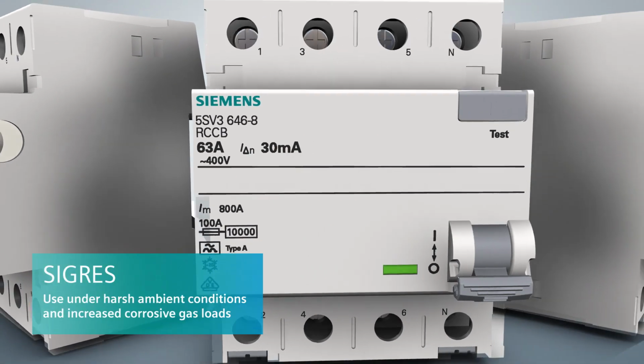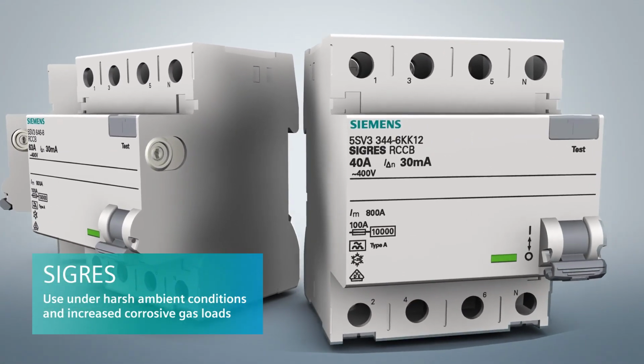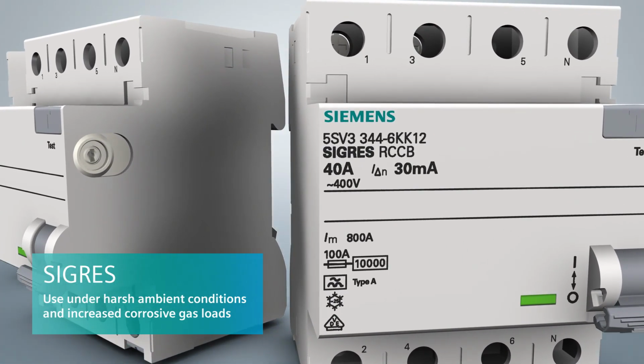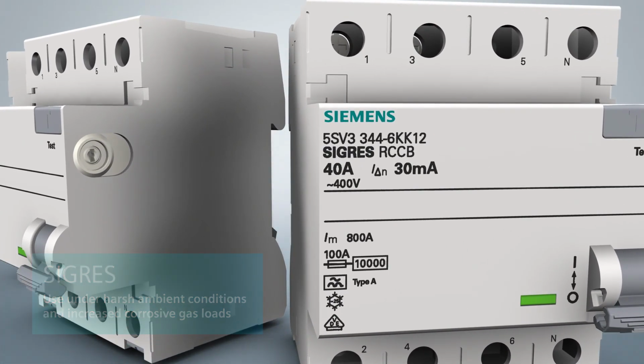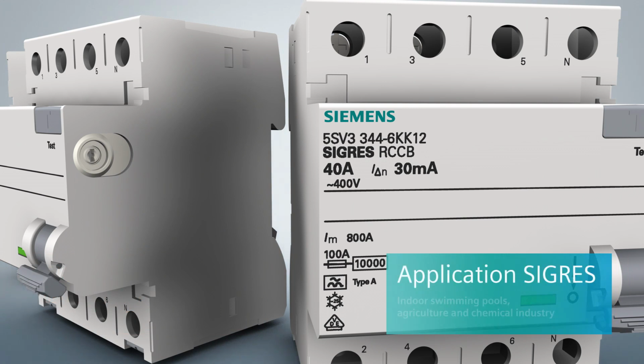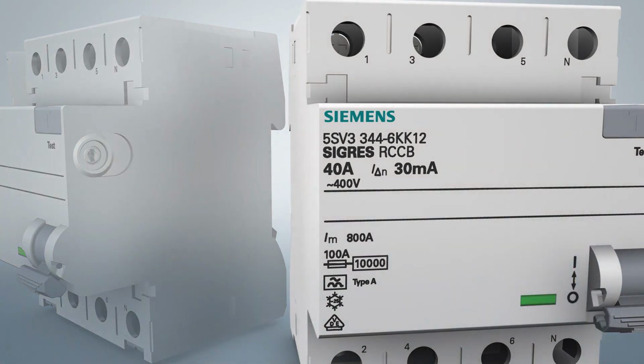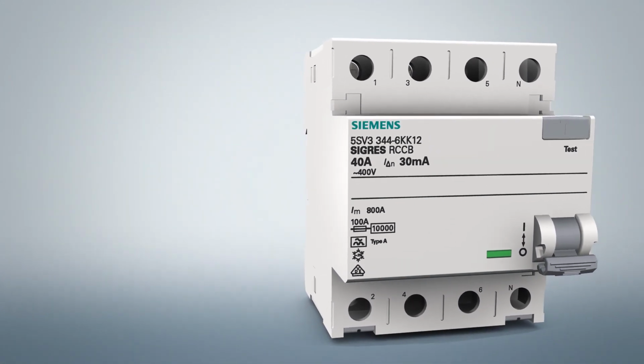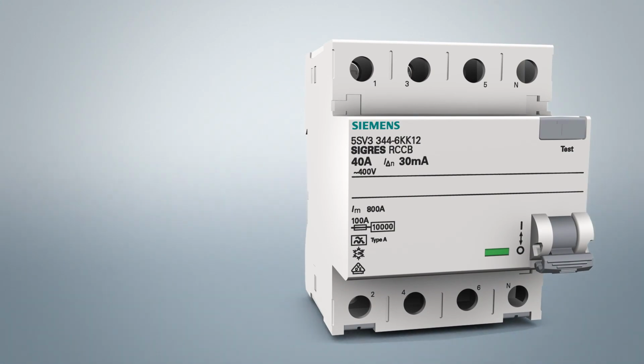The SIGRES residual current protective device was developed for severe ambient conditions with increased corrosive gas loads. Gases in connection with humidity, which frequently occur in indoor swimming pools, agriculture and chemical industry applications, bear a corrosive effect on the device's metal parts and particularly on the metal surfaces of the holding magnet release.